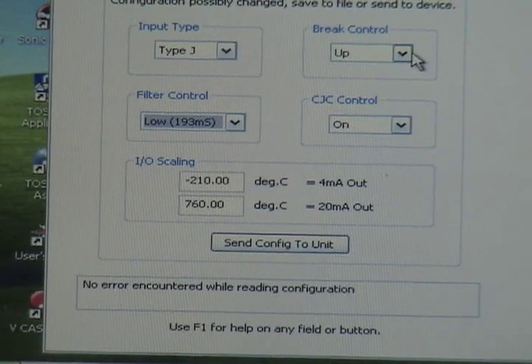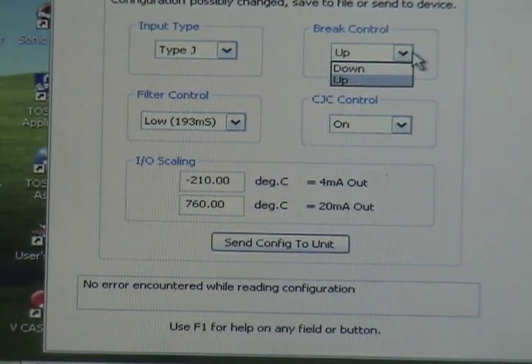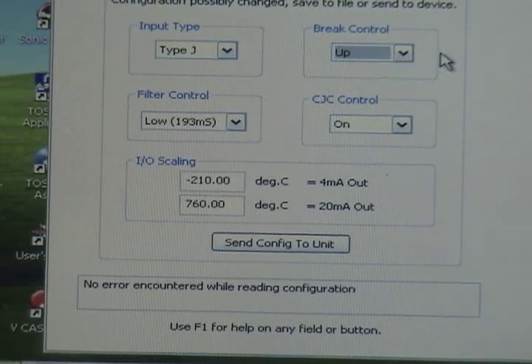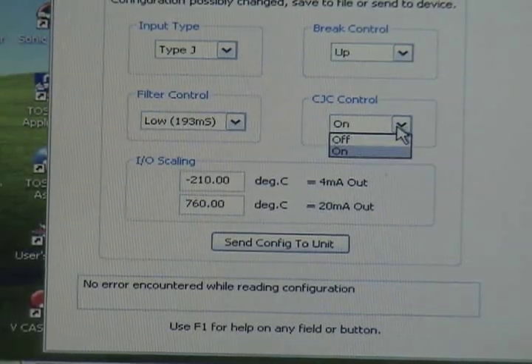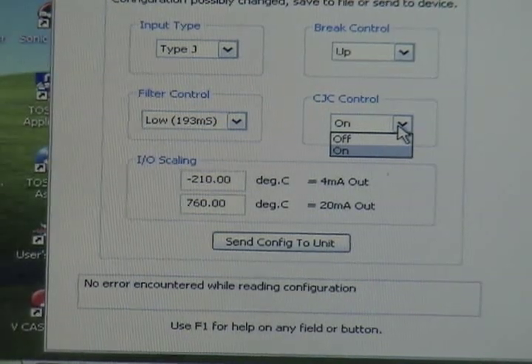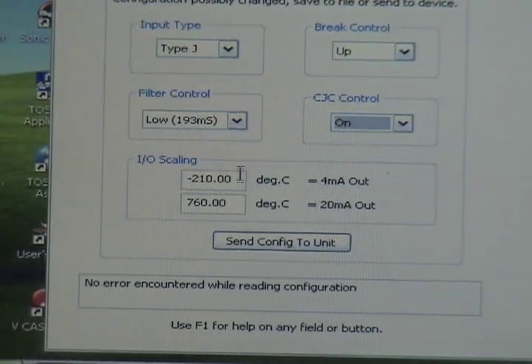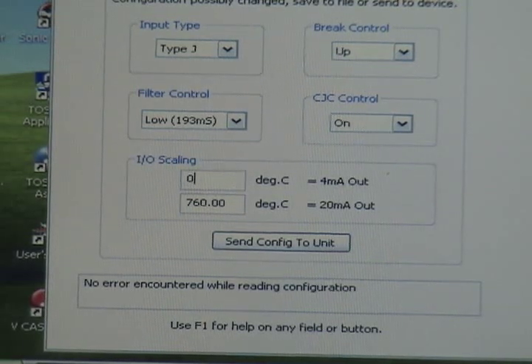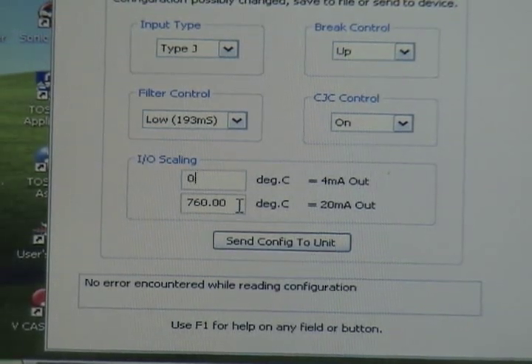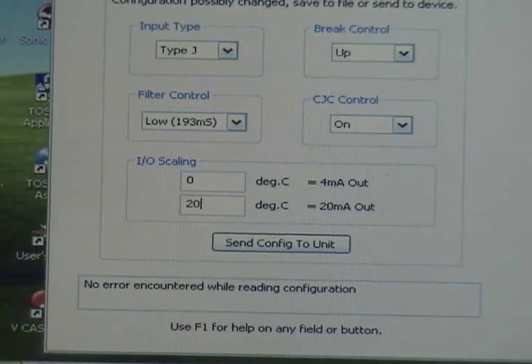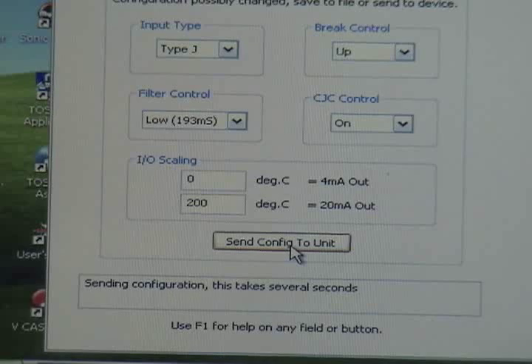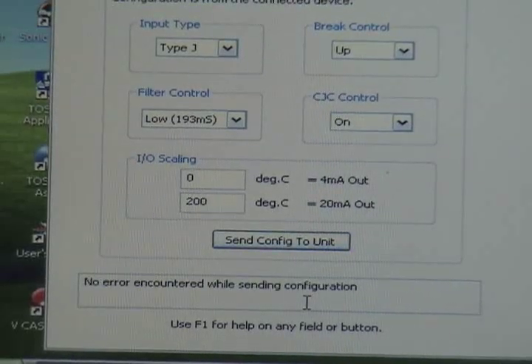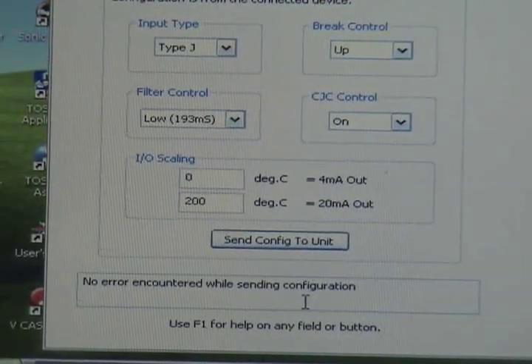The thermocouple break detection is default set to up. I'm going to leave that there as most temperature transmitters go in that direction. And here you have cold junction compensation control. We're going to leave that on because it is a thermocouple input. And the last step down here is your scaling. And for today's demo I'm going to send a configuration into the unit of 0 to 200 degrees C in equals 4 to 20 milliamps out. I click send configuration to the unit. The box at the bottom tells me no errors are encountered so it's in the unit.